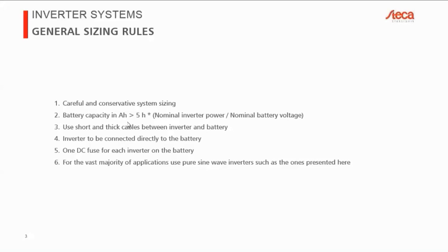times per second. So this is exactly twice the frequency that you have on the AC output. So the battery must be capable of delivering this impulse current. And that's why we need to have a certain minimum battery capacity to ensure that we have a reliable system even in the medium term.